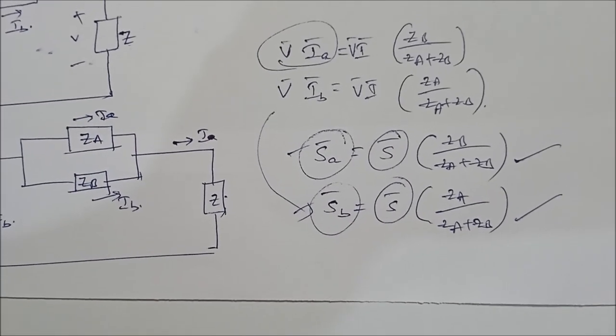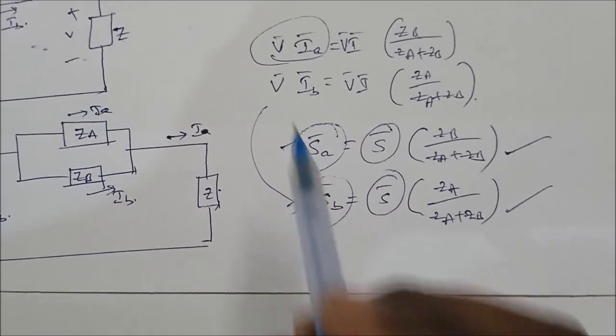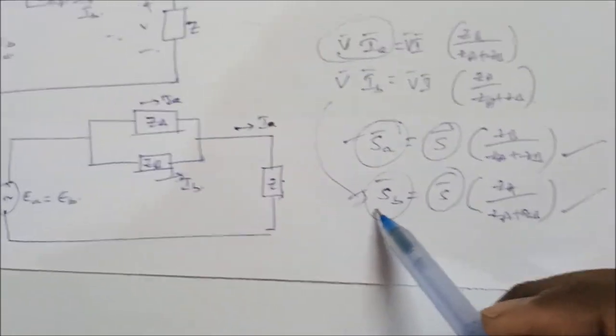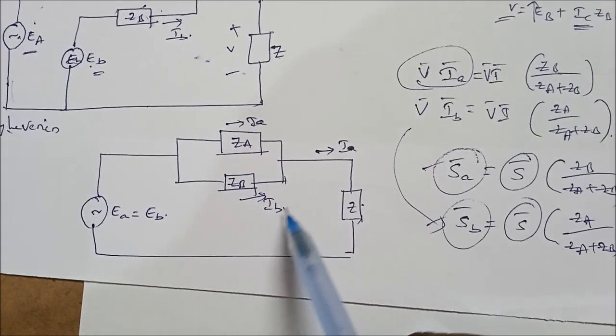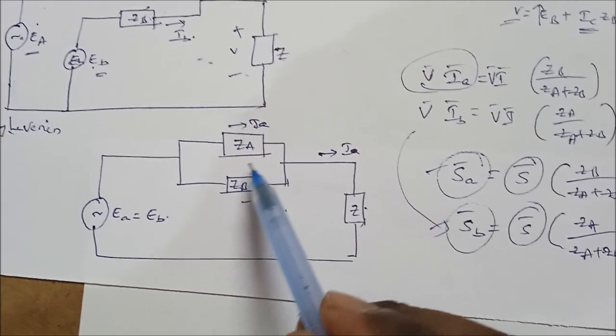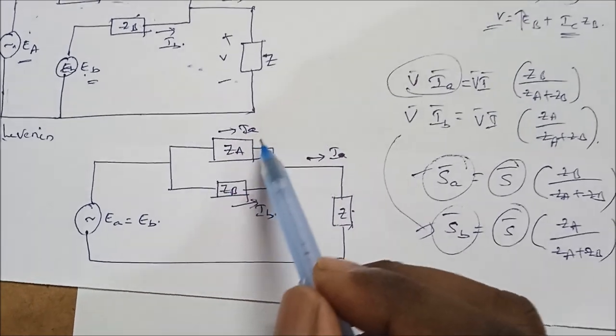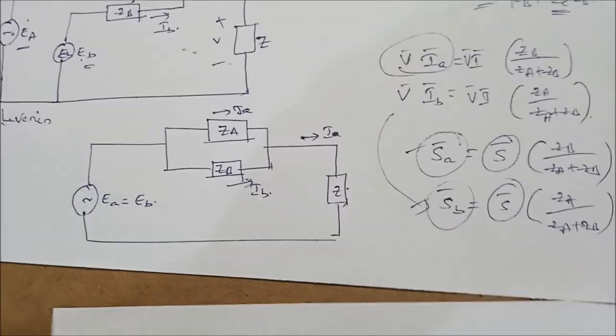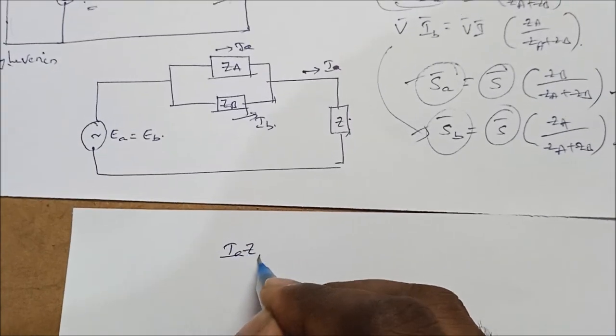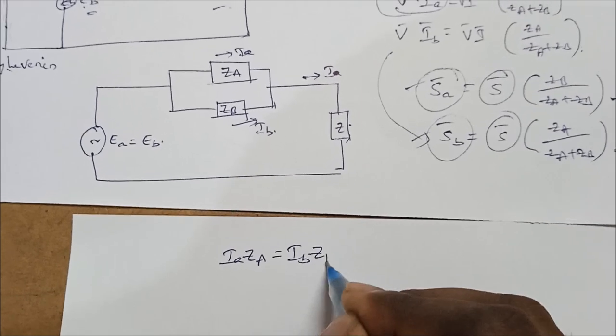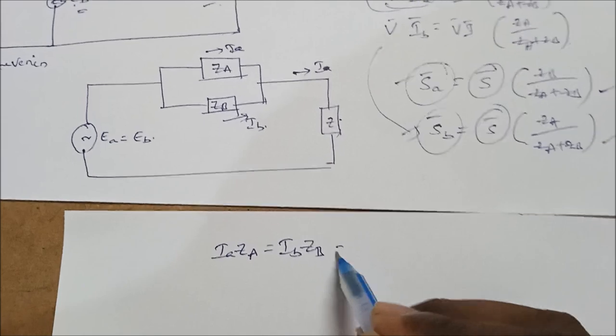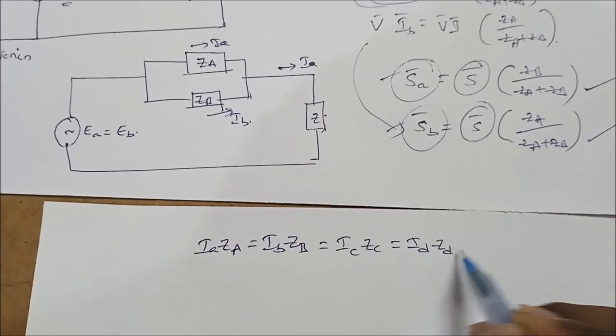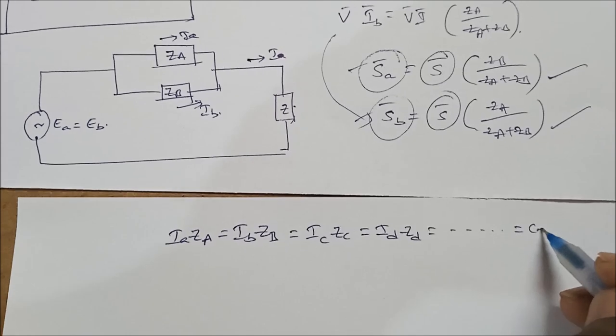Let us continue the parallel operation of transformers. In the last video we derived the equations for Sa and Sb — the load shared by transformer A and transformer B. In the equivalent circuit, Za and Zb are in parallel, so the voltage across Za equals the voltage across Zb. Therefore: Ia·Za = Ib·Zb. If more transformers are present, Ic·Zc = Id·Zd, and all are equal to some constant.